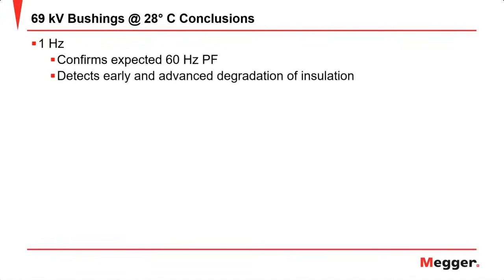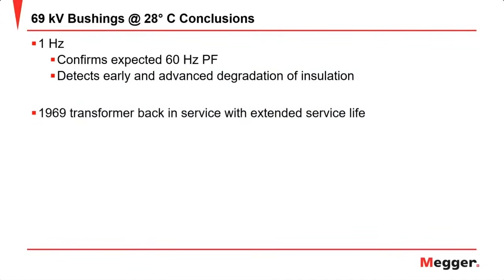So some conclusions from this. With the 1 Hertz, it helps confirm your expected 60 Hertz power factor, and it detects early and advanced degradation of insulation. So again, looking at that third bushing and how it changed significantly at 1 Hertz compared to its sister bushings. And then this transformer was able to be put back into service with extended life, and that these table correction factors are not applicable to 1 Hertz. I didn't really mention it previously, but when you are correcting the 1 Hertz, you have to use ITC. There is no other way, because those temperature correction tables only exist and are only applicable to 50 and 60 Hertz.